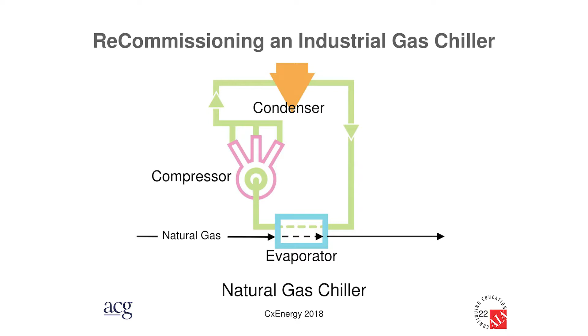So this is a typical refrigeration cycle. The refrigerant starts here, it gets compressed, it goes clockwise through the air-cooled condenser and cools off. Then it goes through a thermal expansion valve and through the evaporator, which is that shell and tube heat exchanger I mentioned. And the way this works is that the natural gas goes through the evaporator and it gets chilled as it goes. The chiller skid is actually 4 separate compressors and refrigeration circuits.